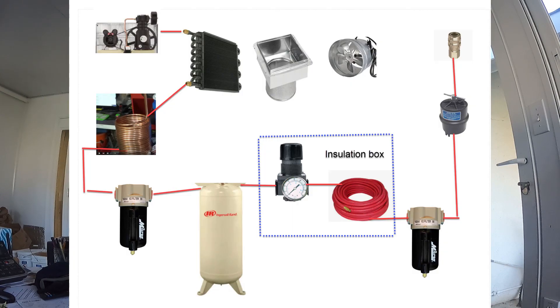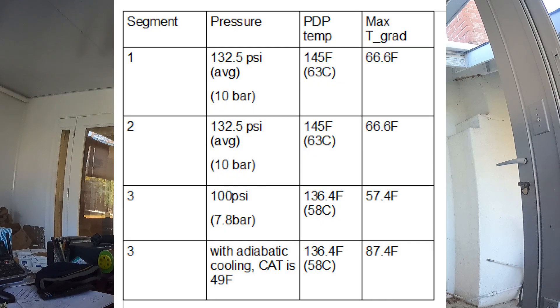Section three design: the tank has a discharge pressure regulator set to 100 psi. The compressed air temperature should be less than or equal to OAT plus 5°F by the time it gets to segment three. The air is then ported into a post-tank condensation coil. If the compressed air temperature is below the pressure dew point temperature, it will continue to condensate water in the condensation coil. When we regulate the air down to 100 psi, the expansion of the air cools the air due to adiabatic cooling, which increases the max T-grad and improves drying efficiency. This can be a problem in the winter as freezing in the condensation coil is possible.